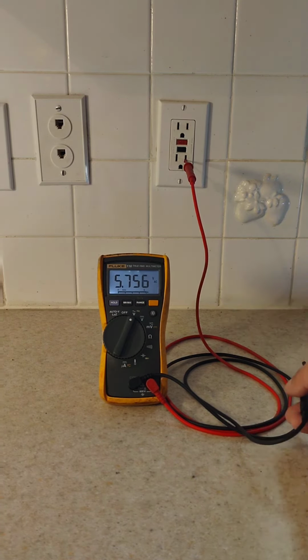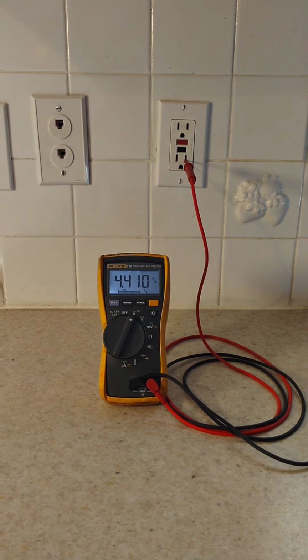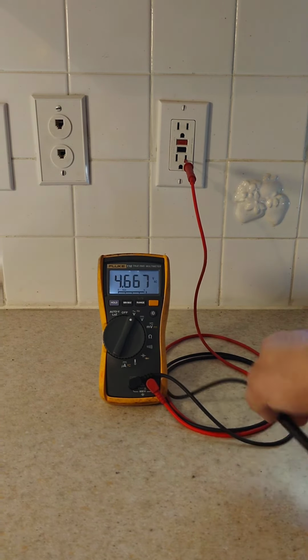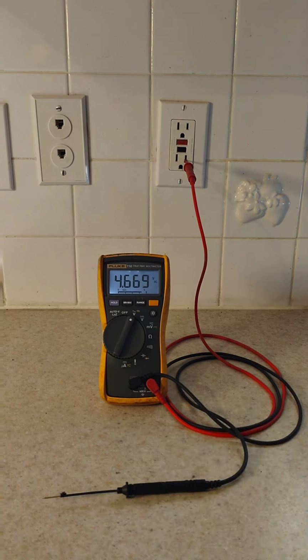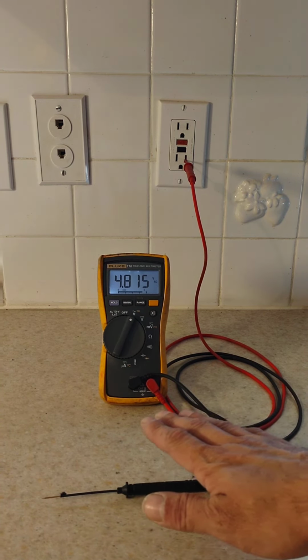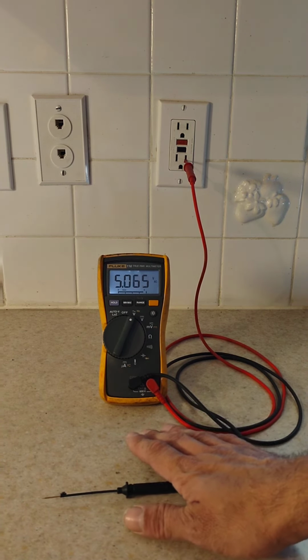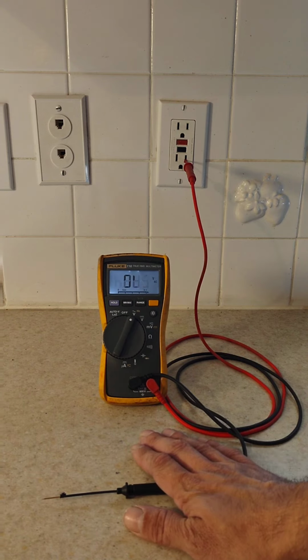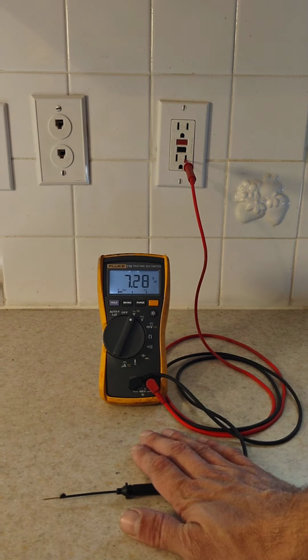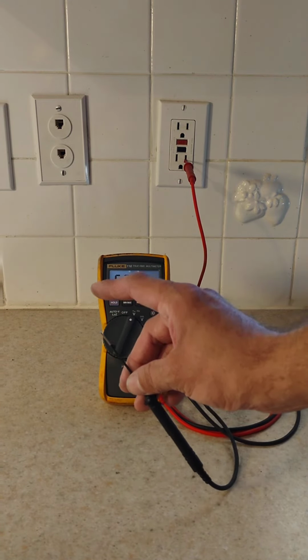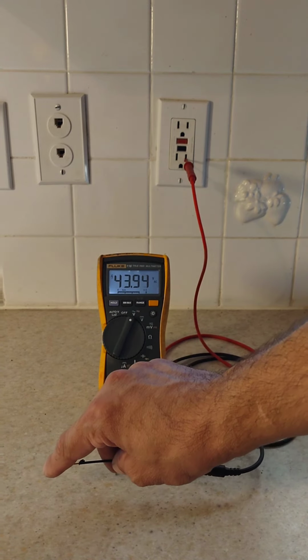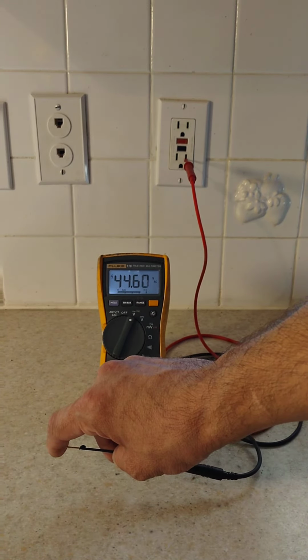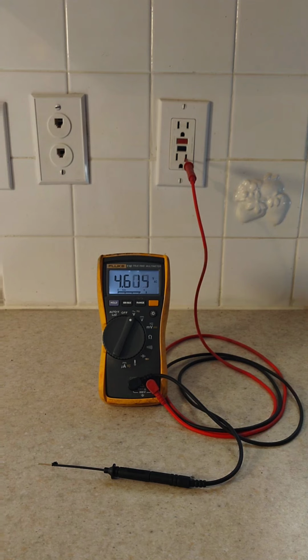This is ghost voltage, and a couple things to notice about it. As I touch the probe, even if I don't touch the conductor, as my hand gets closer to it, notice that the displayed voltage goes up, 5, 6 volts, almost 7. And if I do actually touch my probe, which is, in this case, electrically safe, now it shows 42, 44 volts. That's the definition of ghost voltage.